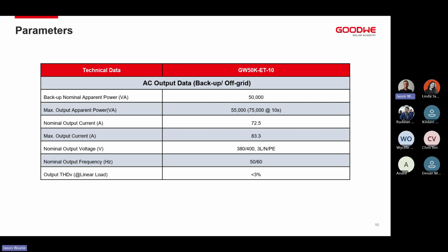Just going back to that, often we get questioned about what happens if we have a load of 60 kilowatts, for example. Does it mean that we'll be able to overload the system for maybe 30 or 40 seconds as opposed to 10 seconds? Hardware-wise, yes, it will be able to handle it for a longer time because the DC capacitor bank will take a longer time to discharge. On the software or firmware side of things, no, it is capped to a 10-second overload time to protect the inverter itself and obviously to protect the loads on the output side, to protect your cables as the installer running the system.